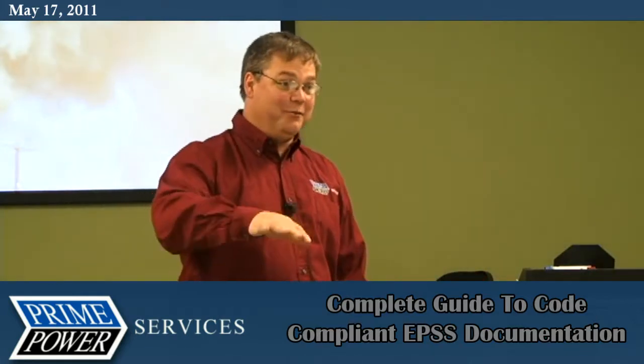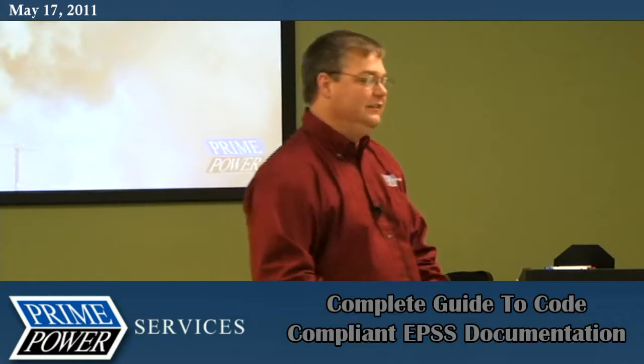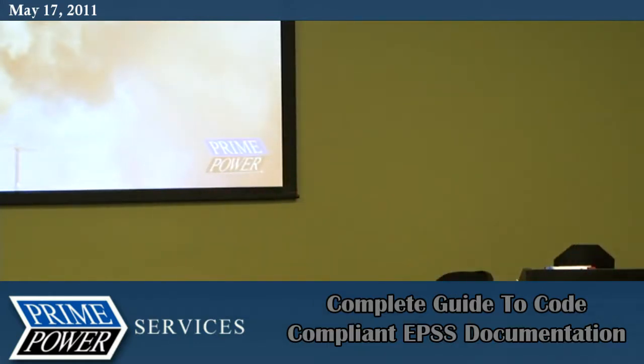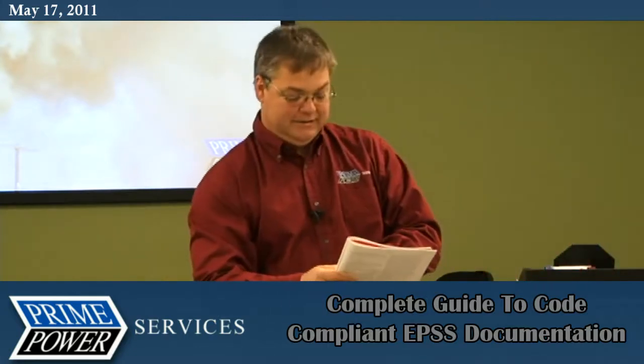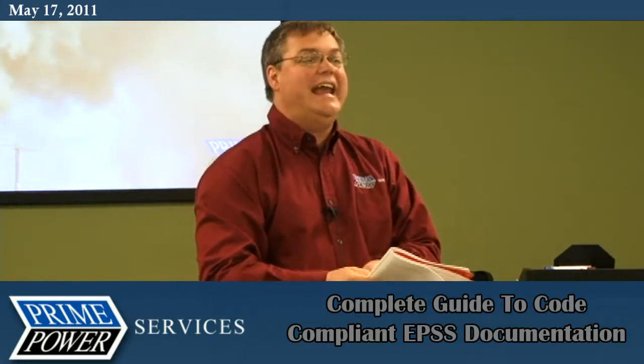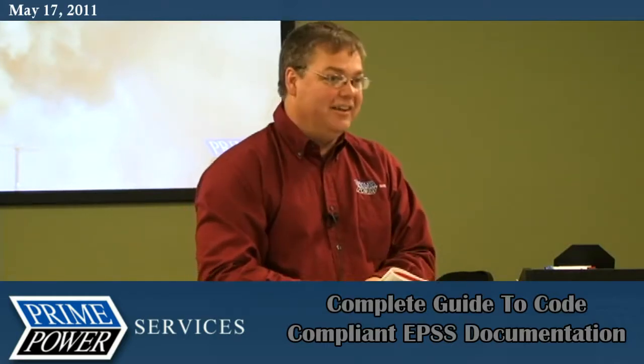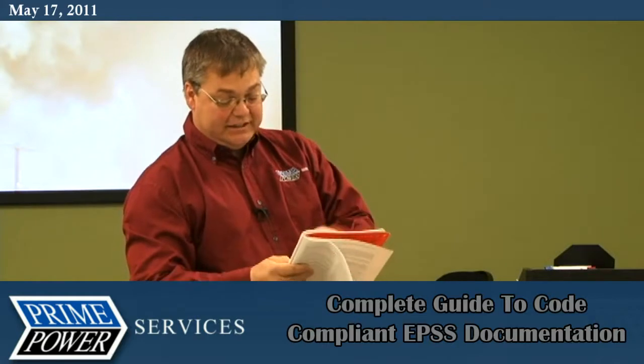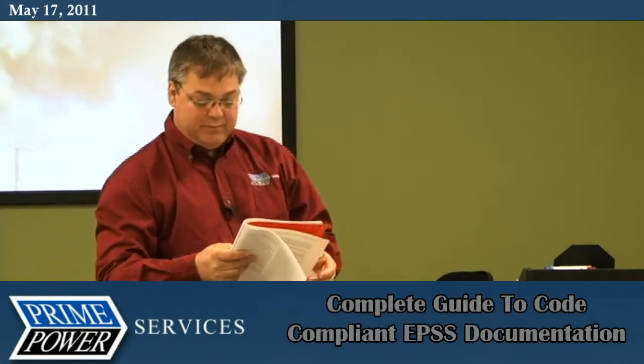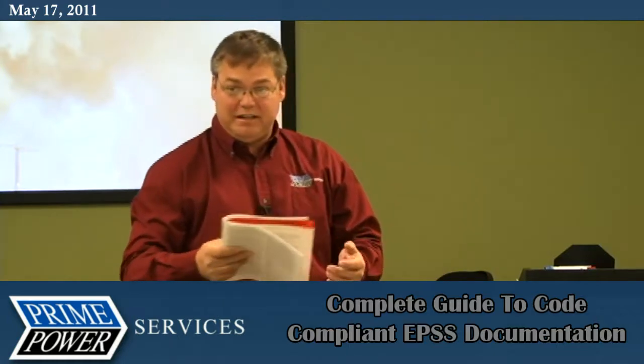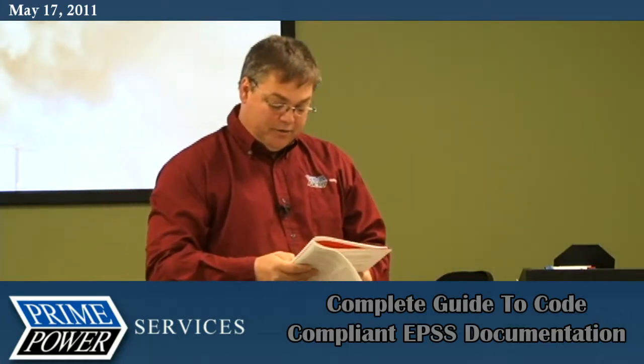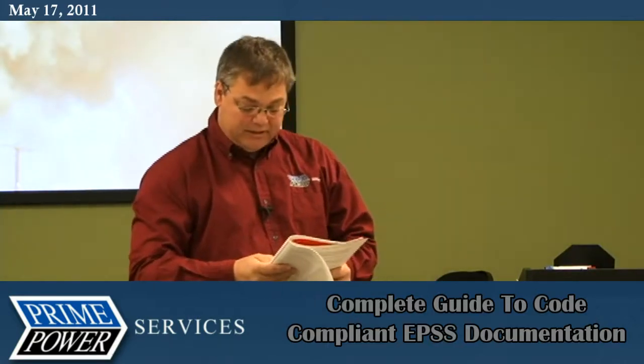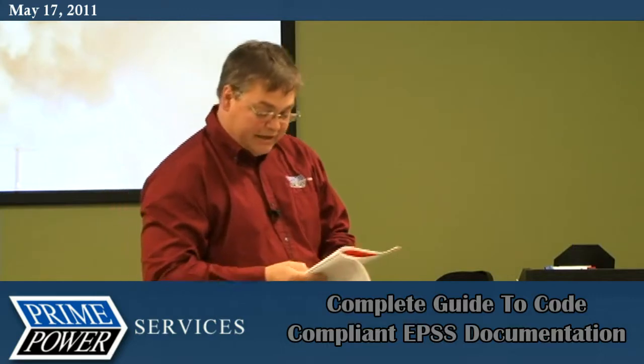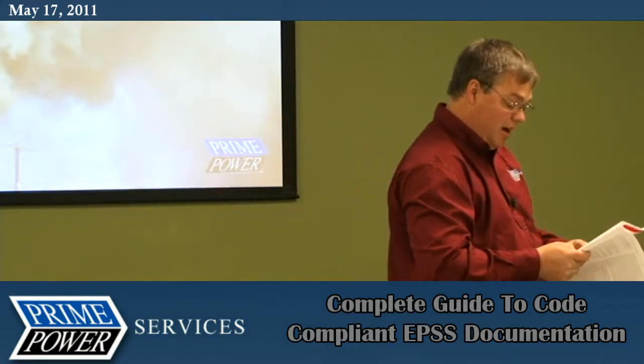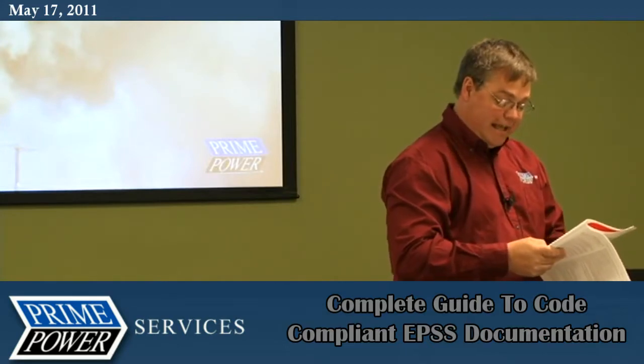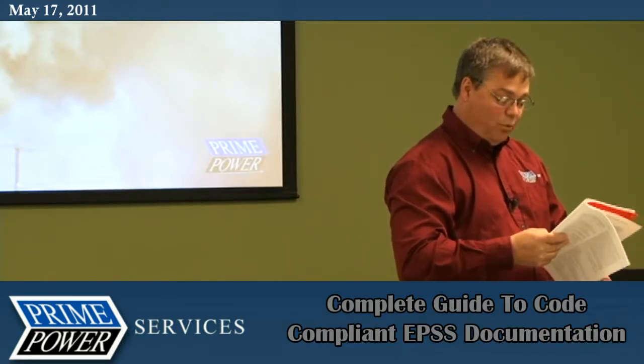So you've got a few options, depending on where you are. Let me see that, if you don't mind, Chris. So if you get it up to temperature, you don't have to run it. And here's the key: diesel generator sets in service shall. That's not a should, that's a shall. In other words, you have to do this. Be exercised at least once monthly for 30 minutes, loading that maintains the minimum exhaust gas temperature as recommended by the manufacturer, and you can find those now, under operating temperature conditions at not less than 30% of the nameplate. If the engine cannot be loaded as required in Section 2, the engine shall be operated until the water temperature and the oil pressure have stabilized, and then the test shall be terminated before the 30-minute time period.